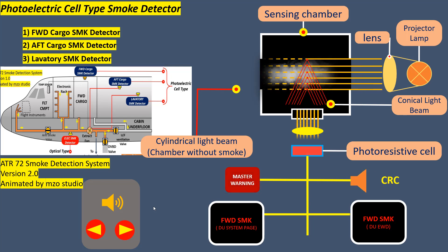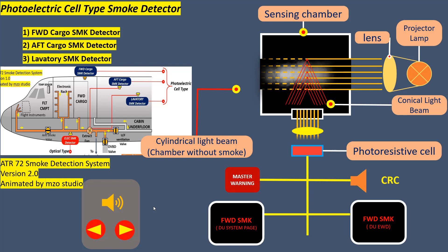As soon as smoke penetrates into the sensing chamber, it influences the light beam, which deflects and diffuses it. A conical refraction is produced and the photo resistive cell is reached by light. As long as there is smoke in the sensing chamber, smoke diffracts the light and the photo resistive cell keeps the warning light on.